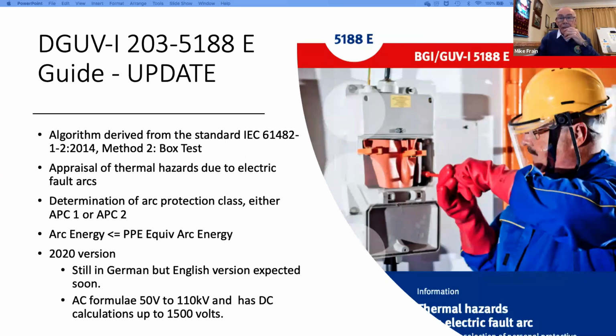So they're both expressed in kilojoules. So if you get an incident, if you get the equivalent arc energy, which is higher than arc protection 1, but lower than APC 2, then you would wear PPE according to APC 2. Obviously, they don't provide incident energy calculations, and you can't make a direct comparison between the DGUV standard and IEEE 1584. But it is in use within Germany, particularly, and France.